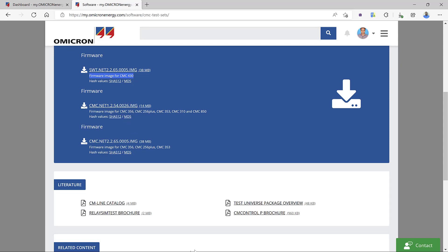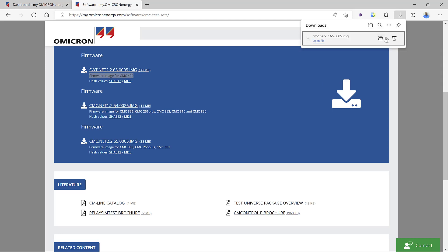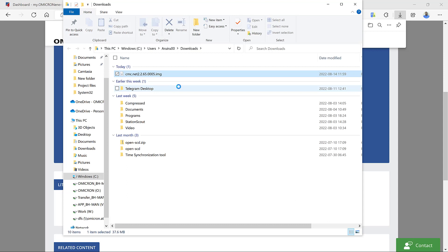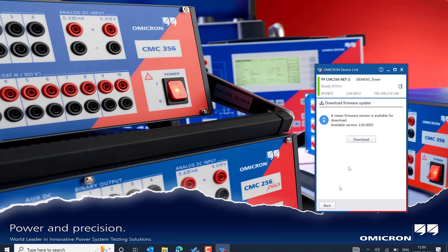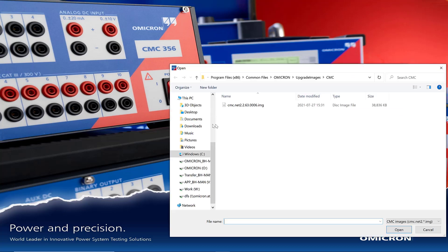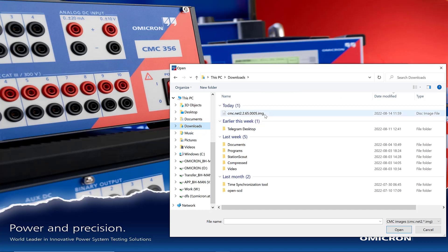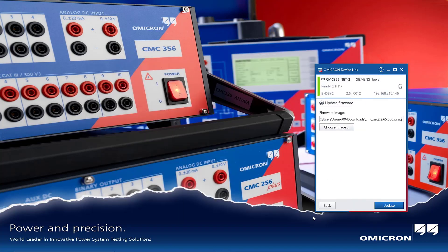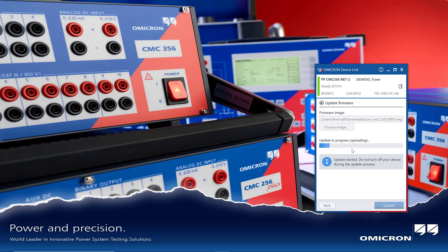Coming back to the downloads folder, the firmware image has been downloaded to the default downloads directory. In the Omicron DeviceLink software application, I choose the second option — 'Update Firmware' — and select the image file. It defaults to a different directory, so I navigate to the downloads folder, pick the file, and click open. Then I select 'Update' to proceed, and the update starts automatically over the Ethernet interface.